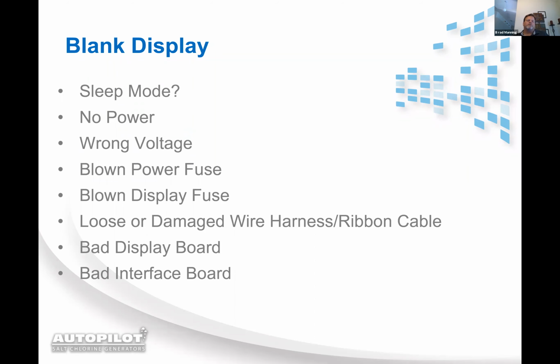You want to check for loose or damaged wiring harness or ribbon cable. Wiring harness is on the older units that don't have an 848 board, and the ribbon cable is for units that have an 848 board. So you want to check that out. There's also a 4-pin connector that comes off of the transformer that plugs onto the 830 board, so you're going to want to check that. You could potentially have a bad display board or bad interface board. You could also have a bad hydraulic circuit breaker, or you could have a bad transformer.